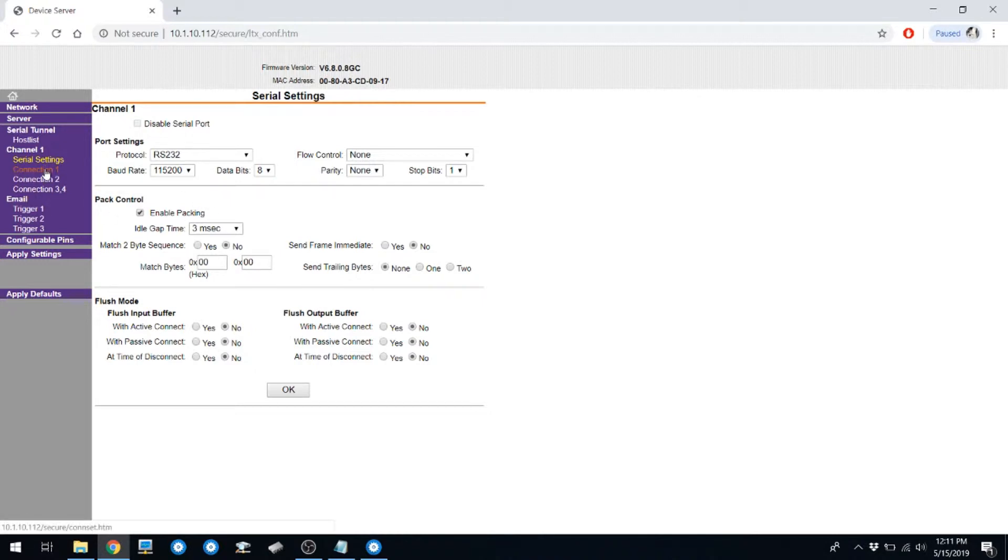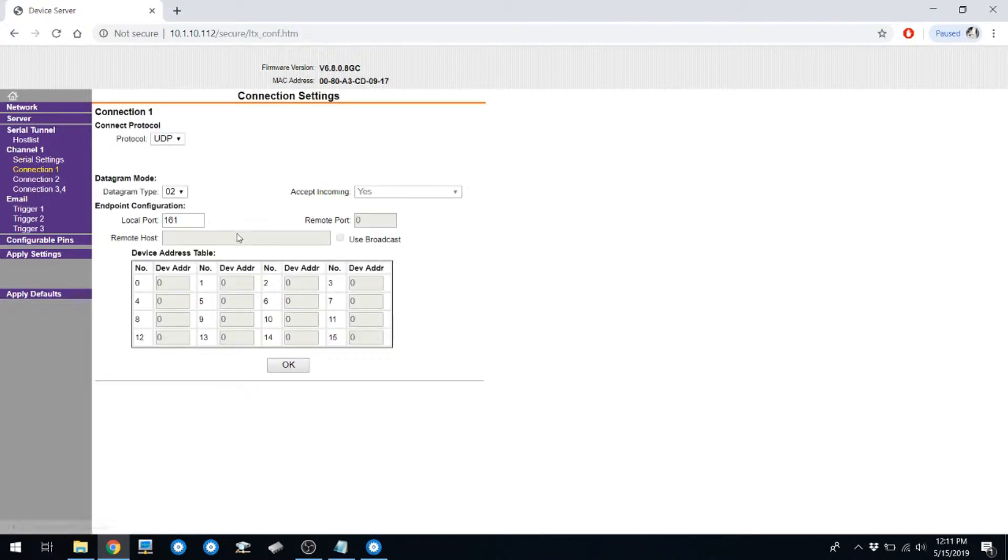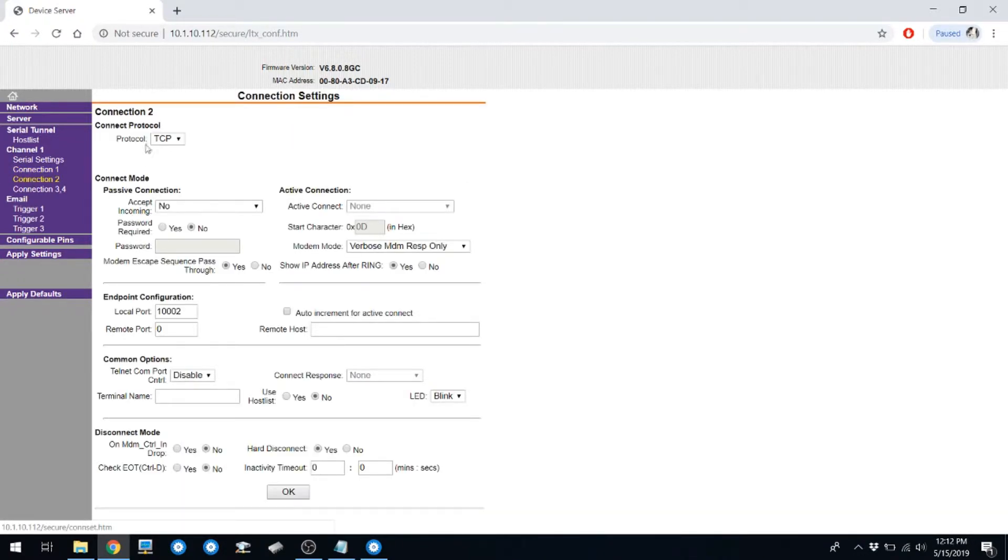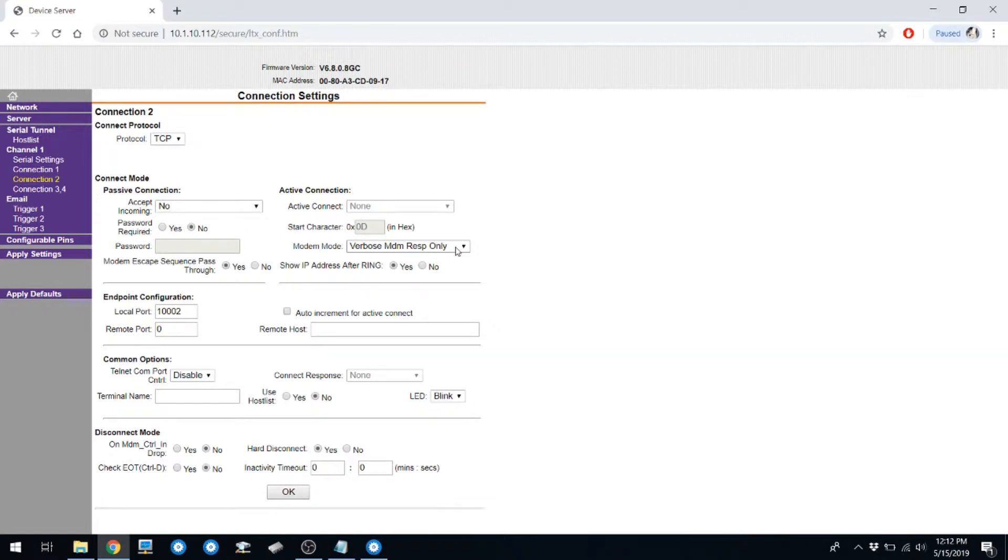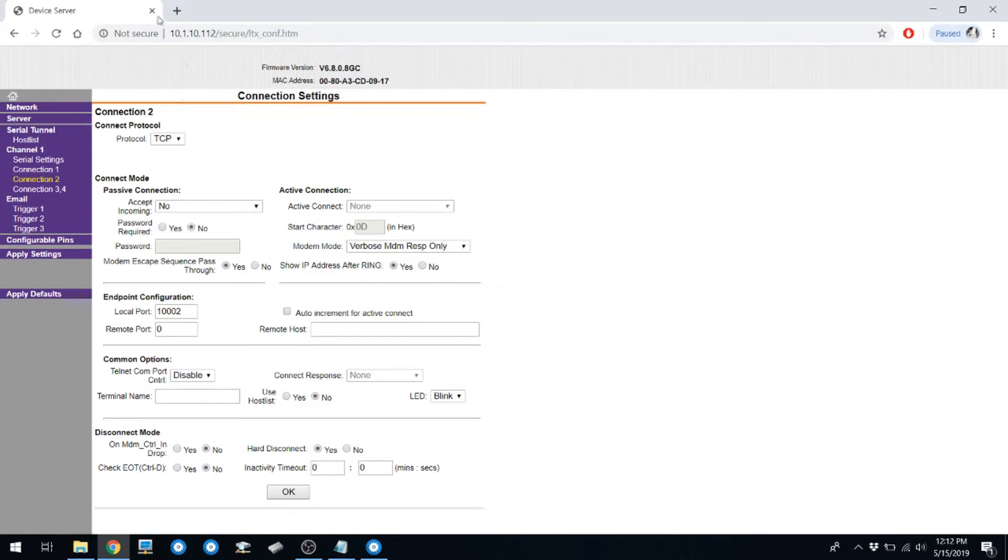You can check your serial settings. You can also check your UDP settings. Your local port should be 161 for this. Your TCP configuration should have modem mode set to verbose modem response only. If modem mode is not set to verbose modem response only, please adjust this setting. If you do have to adjust this setting, make sure you hit OK at the bottom of the page, and then apply settings on the left-hand side of the page.